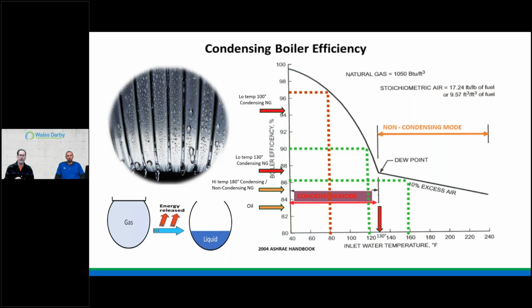But if you look at that 100 degrees, you go up to the dew point, go over to the left, and there maybe you're achieving what the sticker says on the appliance. And to your point, I was just going to make this point, and Eric actually just brought it up. You say how people are afraid of the 180 mark, but when you look at a radiant system, we're running at 100 degrees, 95 degrees, and like Eric said, at -16, they're running most of his radiant, he says, at under 95 degrees.